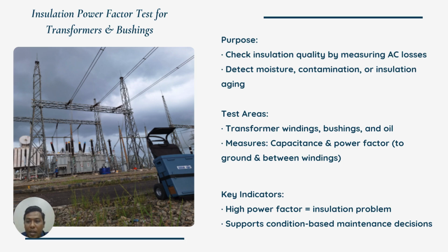This slide covers the insulation power factor test, a key method for checking the health of transformer insulation. It works by measuring how much AC energy is lost. High loss can mean moisture contamination or insulation aging. We run this test on the windings, bushings, and oil. If we see a high power factor, it usually means there's a problem that needs attention. This test helps us find issues early and plan maintenance before anything fails. It's a simple but powerful way to keep transformers running reliably.